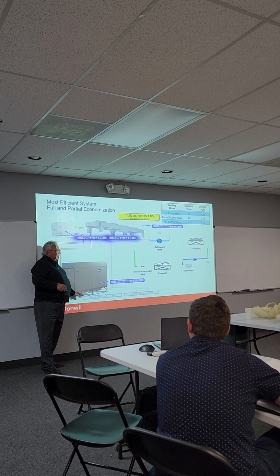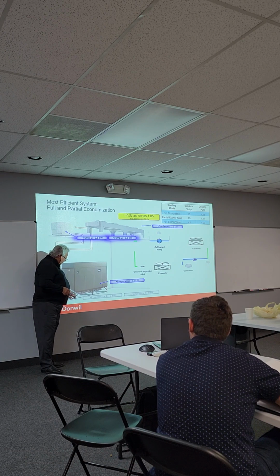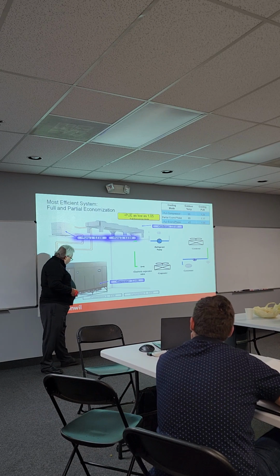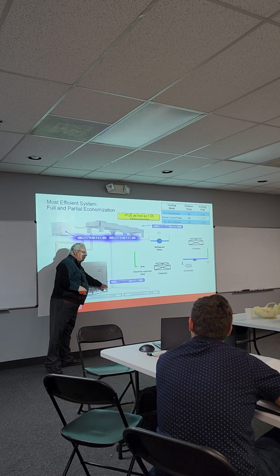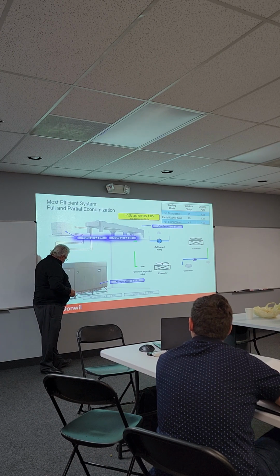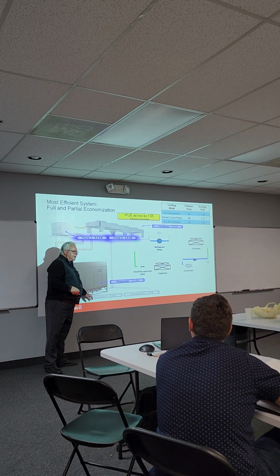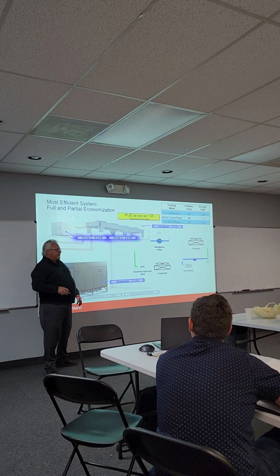So what we found by taking the fans and putting them down out of the unit into the floor is we can increase our efficiency by almost 5%. Is that crazy? Doesn't look like it's going to the floor. Well, remember, the floor would be right here, this would be the floor stand, and if you have room to put the fans in the floor, that's the way to go.